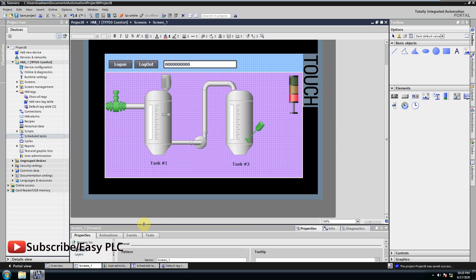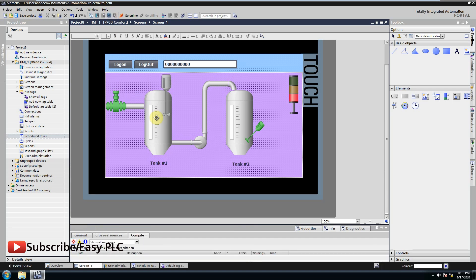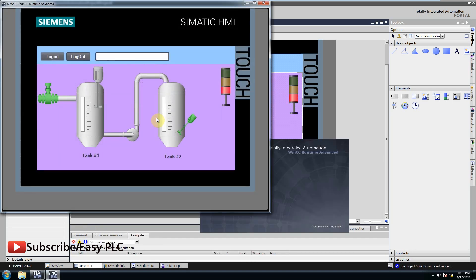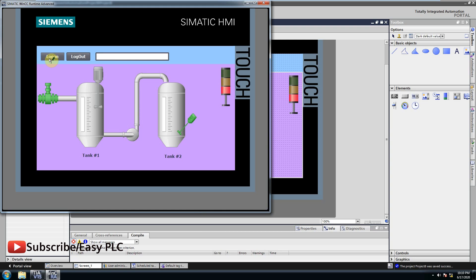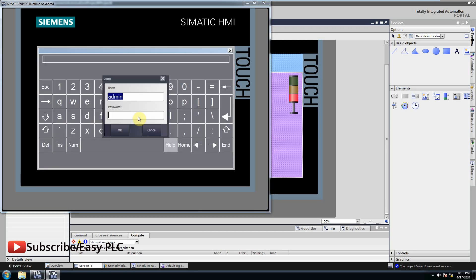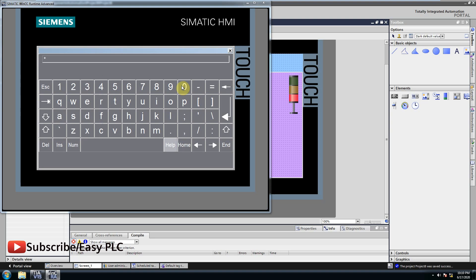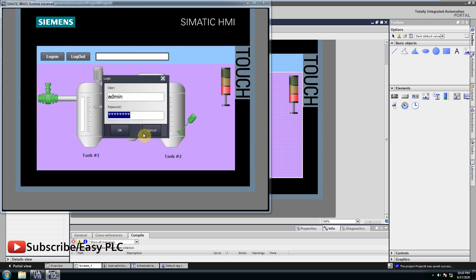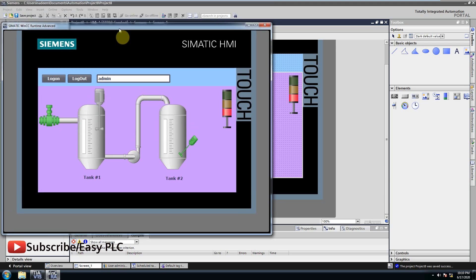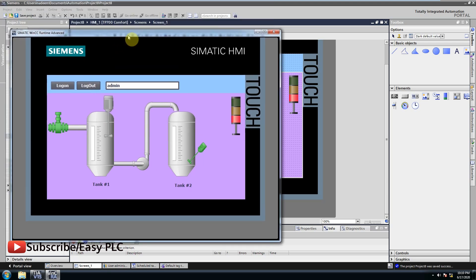Let's run the simulation to see if everything works. As you can see, if I log in on HMI, the schedule task triggered and detect change in user and writes current username in the HMI tag and it gets displayed on the IO field.